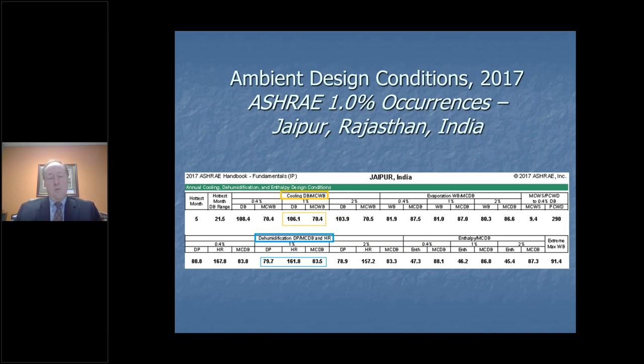And then you'll see in just a minute when we put this on the psych chart, we know two things like we saw earlier. We know the dry bulb and the wet bulb, and we can determine all the other factors. And then what we became aware of, we need to start looking at that peak at other times of the day, which might be the peak dehumidification. It's the dew point with the mean coincident dry bulb and the humidity ratio. And you'll see these particular numbers right here.